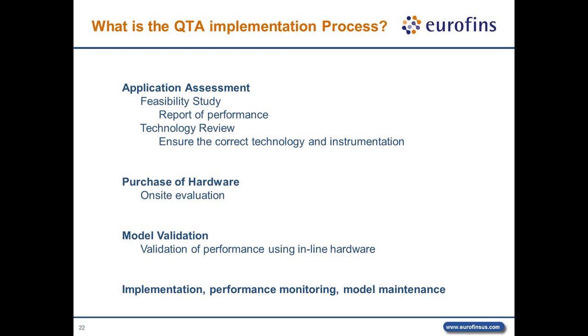With the instrument, fiber optic cables, and probes in place, we continue to fine-tune the models using sample scans taken with the actual components of the system installed. This allows us to capture and treat for additional factors that exist inline. Our validation process compares the results from the QTA models to primary data for a validation sample set. These would be samples that do not currently exist in the models, but are representative of normal production material under production conditions and scanned using the actual inline hardware.